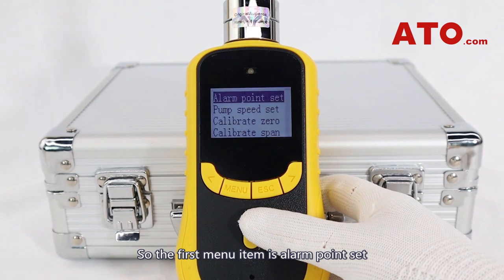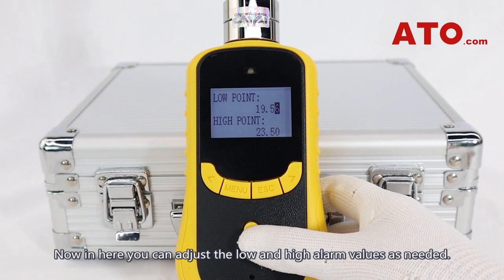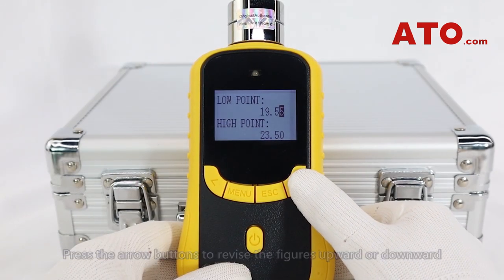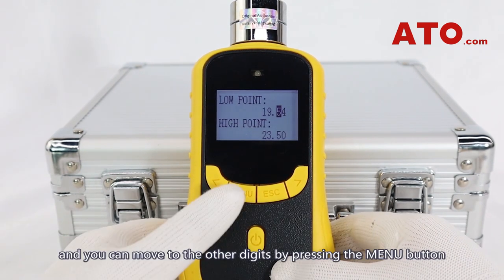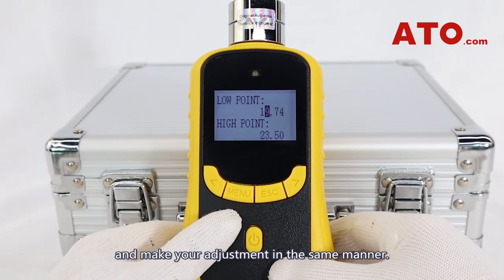The first menu item is alarm point set — hit the power button to select it. In here you can adjust the low and high alarm values as needed. Press the arrow button to revise the figures upward or downward, and you can move to the other digits by pressing the menu button and make your adjustments in the same manner.